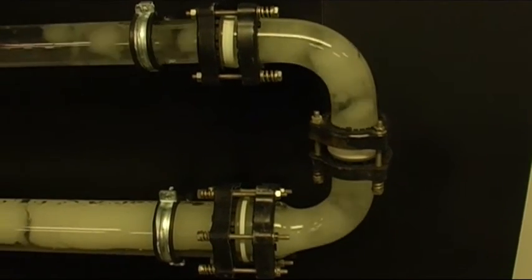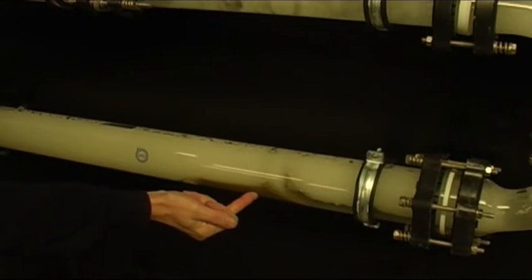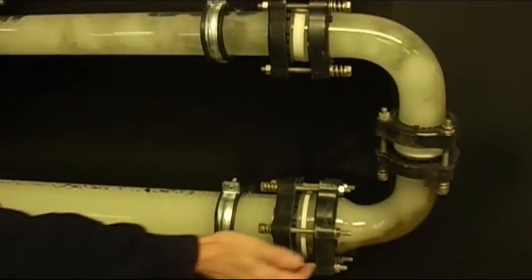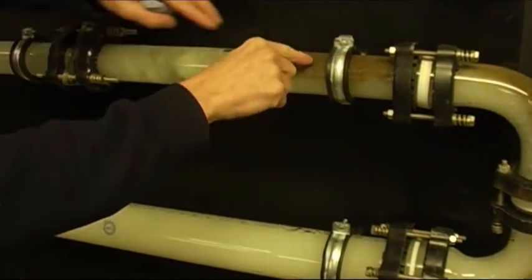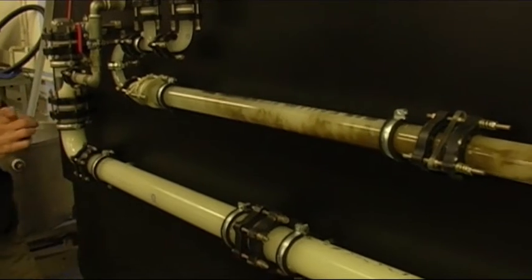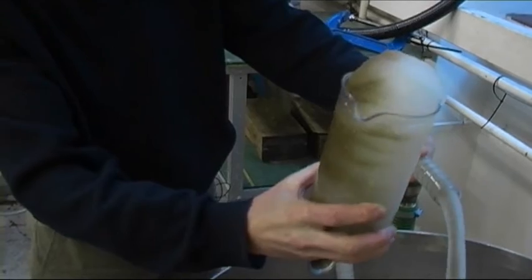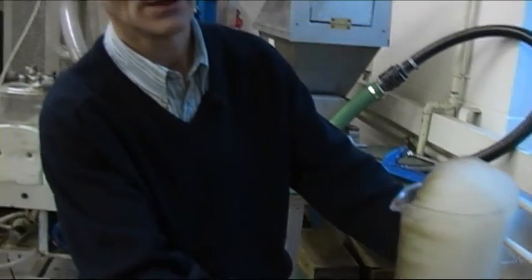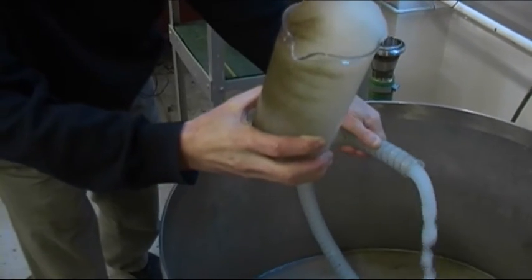Great big dollops of sand being moved by the pig, leaving behind a clean surface. At the moment there's sand here being carried by the pig. The really interesting thing is that the sand is denser, it's on the bottom — as it goes over it wants to be on the top but gravity's taking it down. You can see it rotating, dropping back down to the bottom. The flow rate is the same as the water flush and here's the sand all being taken out — not bulldozed but slowly taken out, so no possibility of any sand getting stuck. It's just transported away happily.